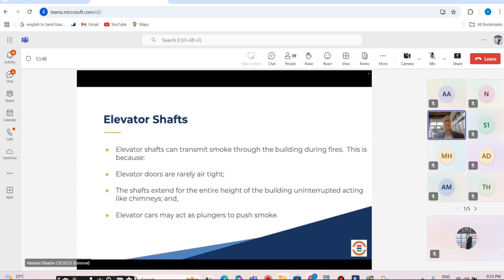Elevator lift well is the most complex system to design because you expect the piston effect, and especially when it comes to fire lift, you expect that fire lift to be on for firefighters to move in and out. At the same time, your pressurization system is activated, you will have a reverse effect. At the same time, when you have a connected lobby also pressurized, you will also see that some of the openings will be a hindrance for your pressurization. So the expected differential pressure that you want to build into the elevator lift well shaft is not possible when you don't design it right.